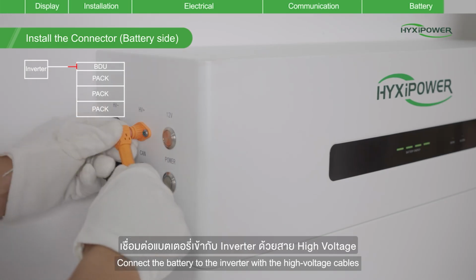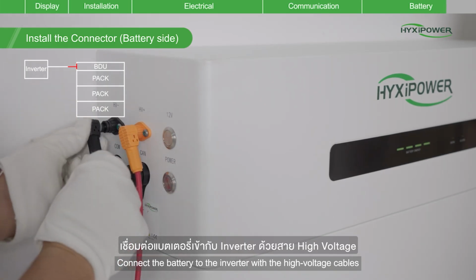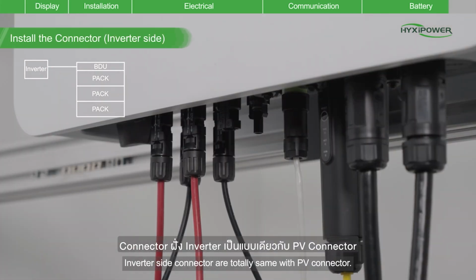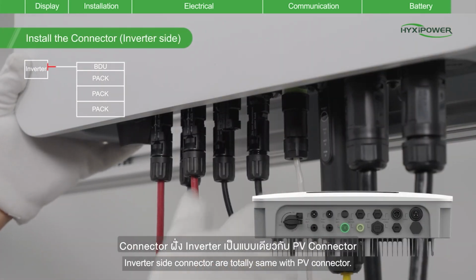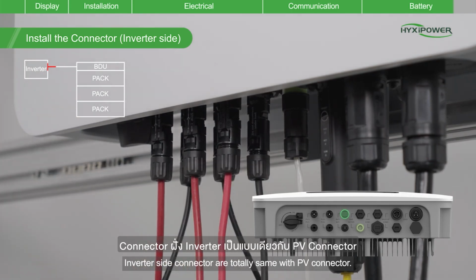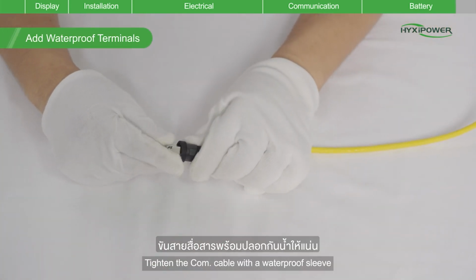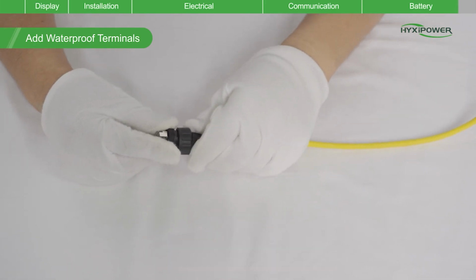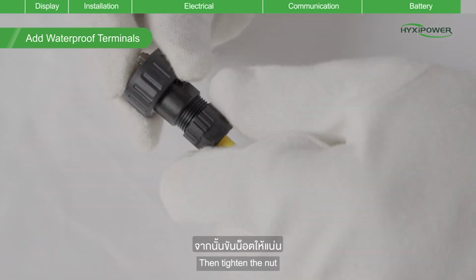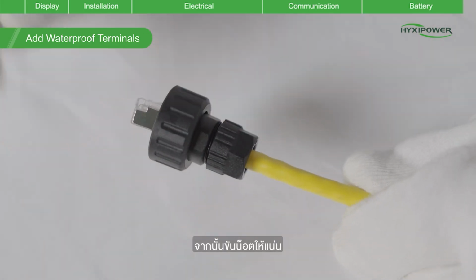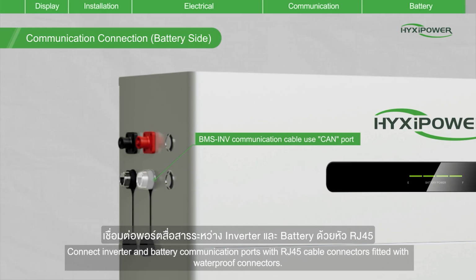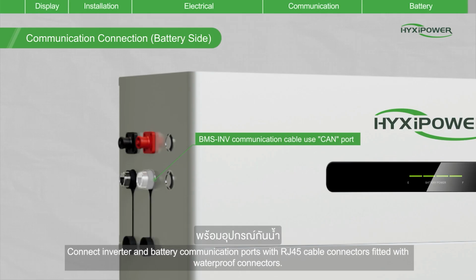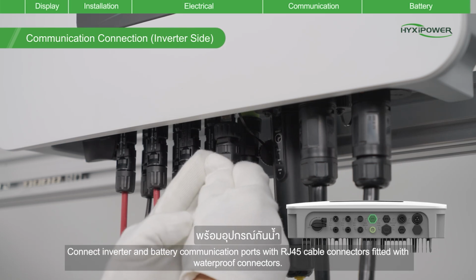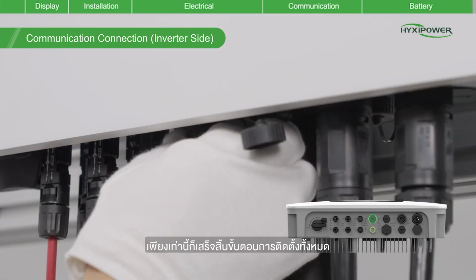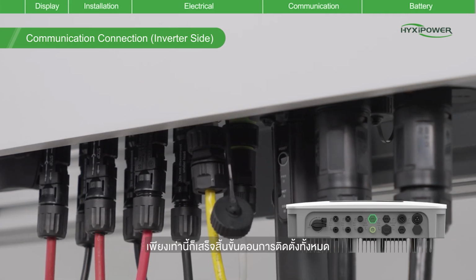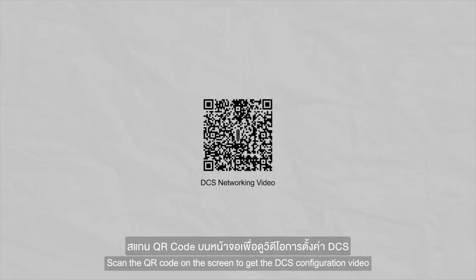Connect the battery to the inverter with the high voltage cables. The inverter side connector is exactly the same as the PV connector. Tighten the communication cable with the waterproof sleeve. Then tighten the nut. Connect the inverter and battery communication ports with RJ45 cable connectors, fitted with waterproof connectors. Then complete all the installation. Scan the QR code on the screen to get the DCS configuration video.